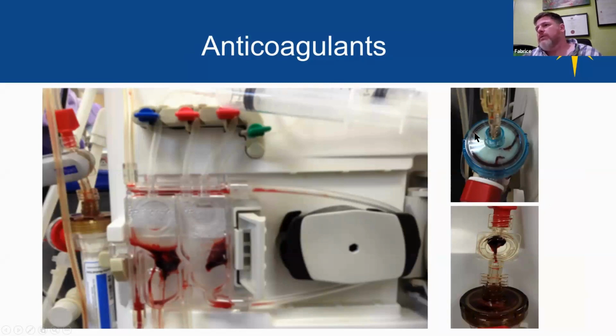Those are the header of the dialyzer, so the top of the dialyzer, and you have those huge clots here. This is the crit line. It's a part that we use for monitoring. There's also a huge clot here. When you see those, and that's something we need to inspect after each treatment, it means also that your dialyzer is full of clot. And that has a huge impact, because it means that your treatment will not be efficient. So that can drastically increase the time of treatment of your patient.